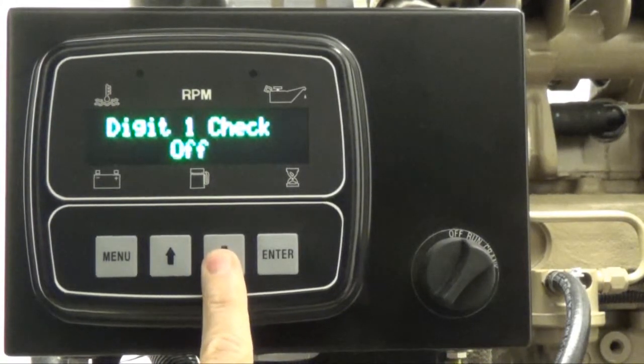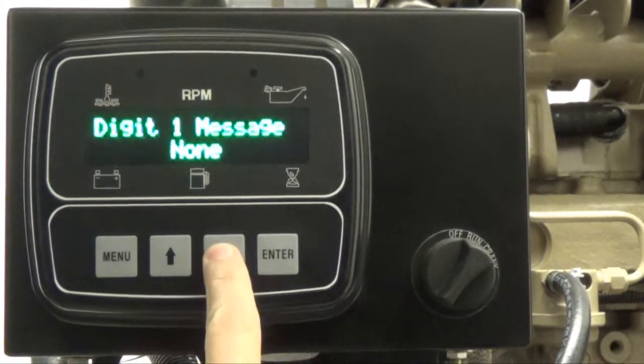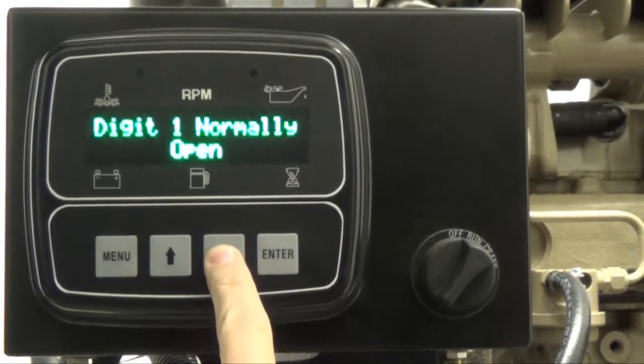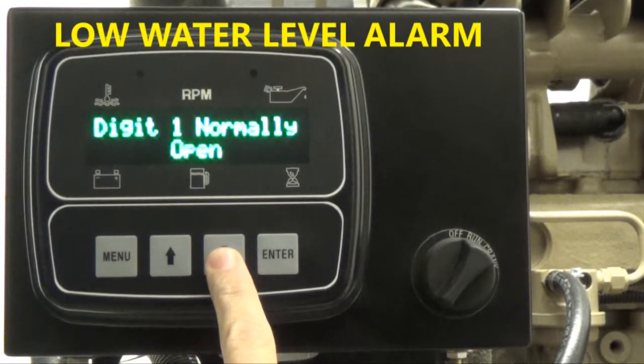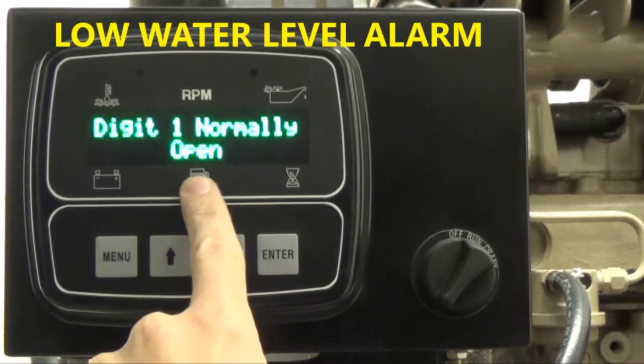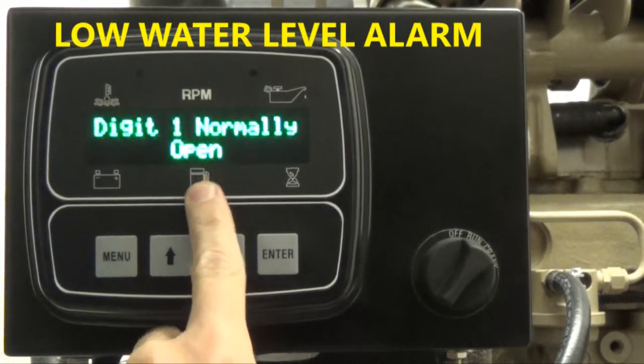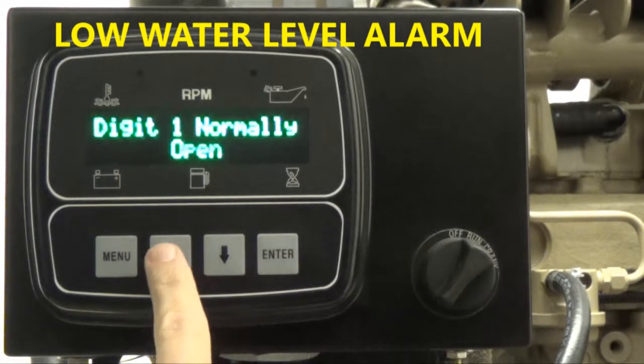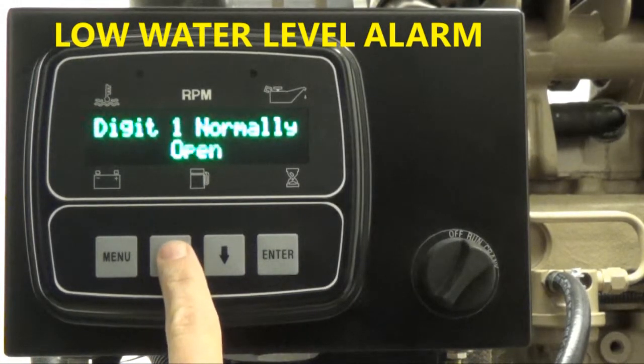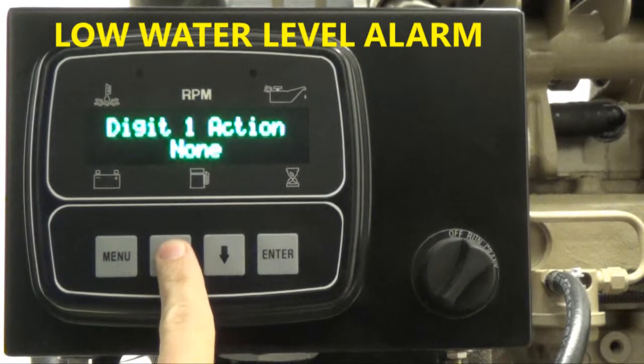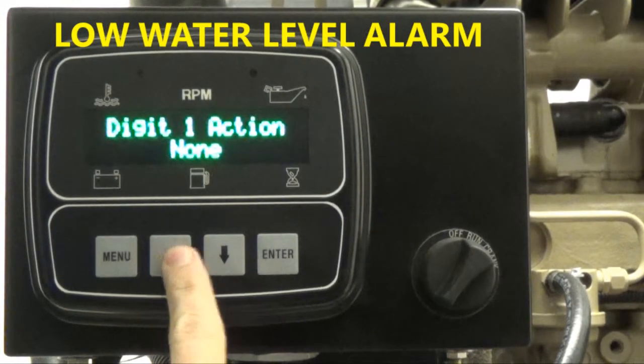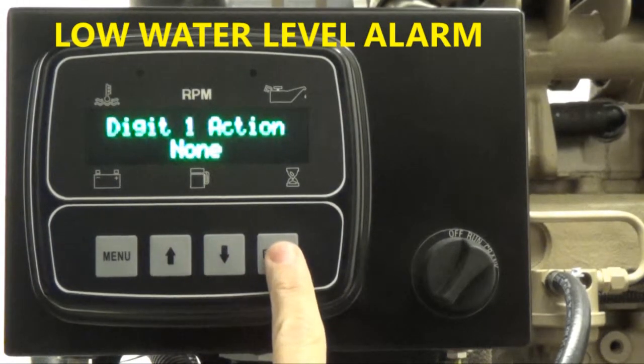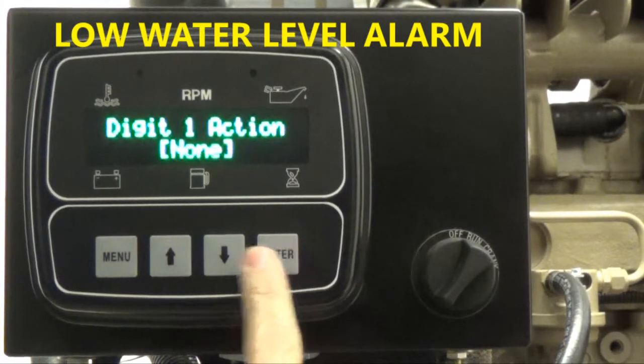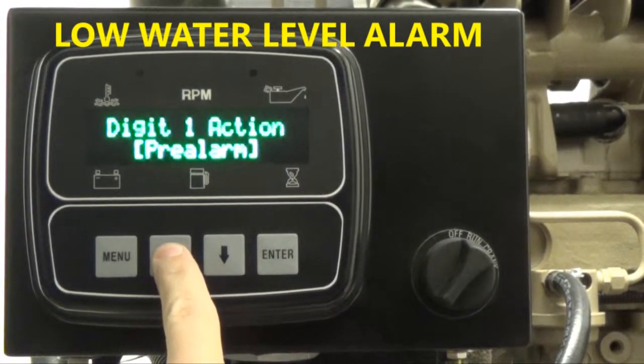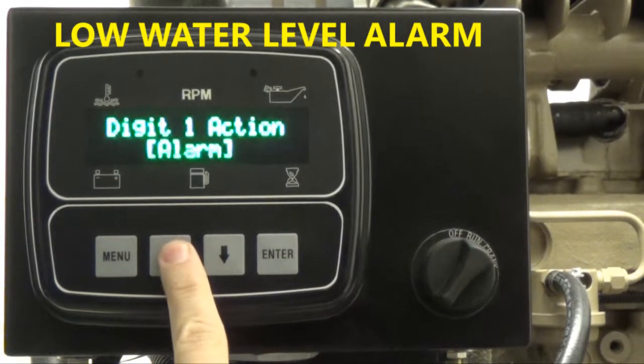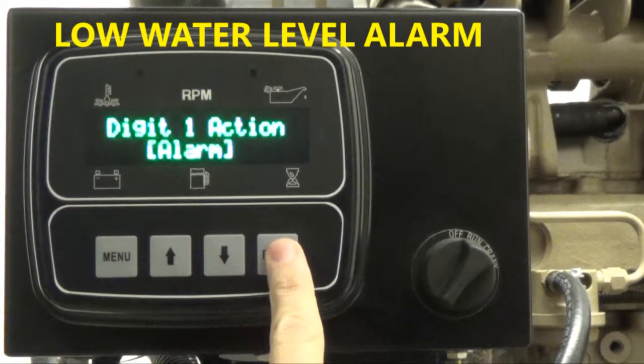For an example, in this video, we will assign a low water level alarm to digital input 1. A low water level alarm would require a normally open switch. Therefore, you would leave the state of the input as normally open in the digital 1 input option. Then press the up arrow button to view the current digital 1 action. To adjust the digital 1 action, press enter and brackets will appear. Keep pressing the up arrow button to cycle through the various actions until you reach alarm. Then press enter to remove the brackets.